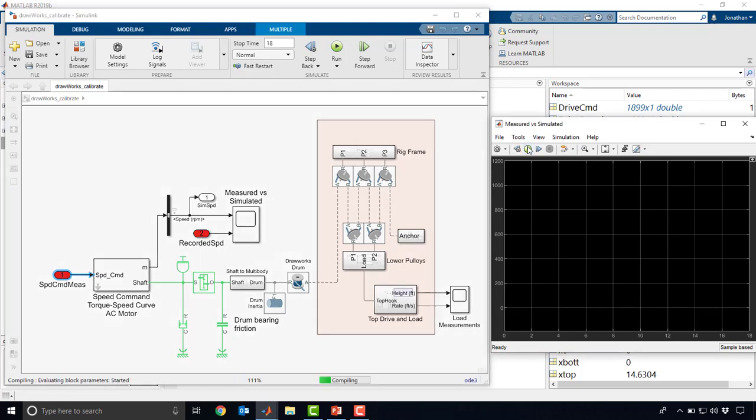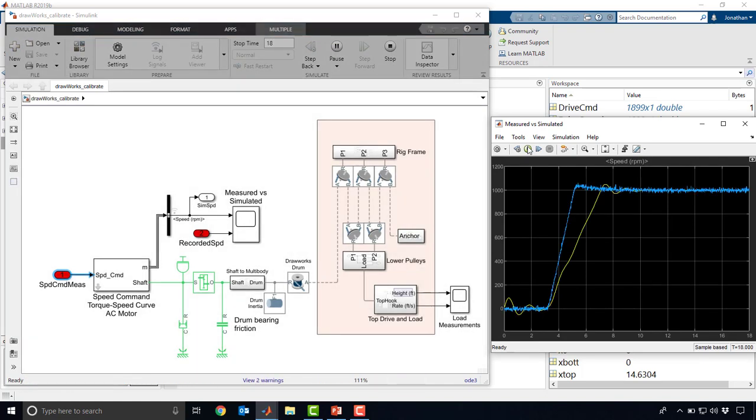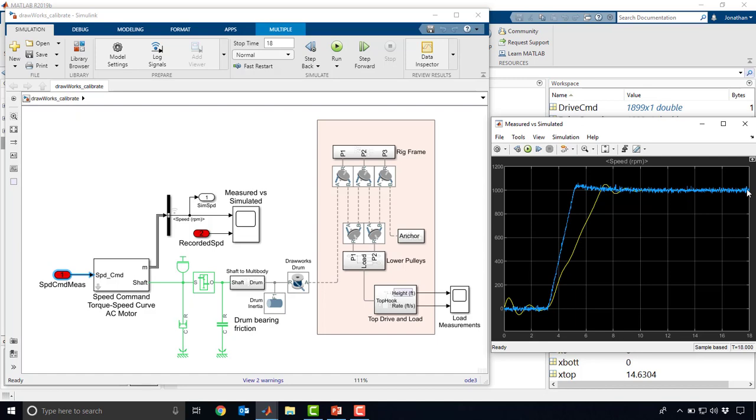I'm going to go ahead and run this simulation given the data that we've pulled in. This data is just in my MATLAB workspace, that's where I'm feeding it in from. We'll see this blue trace, this is the measured data from the field, that's our speed response from the actual drive. And you'll see this yellow simulated trace here is our current simulation response. We have pretty good steady state response matching, but we don't really have good transient response matching.